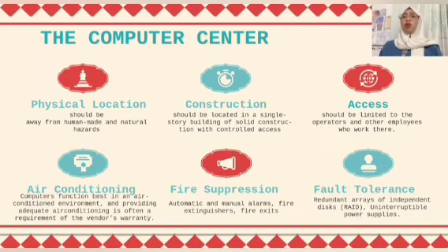The physical location of the computer center directly affects the risk of destruction from a natural or man-made disaster. To the extent possible, the computer center should be away from human-made and natural hazards such as processing plants, gas and water mains, airports, high crime areas, floodplains, and geological faults. The center should be away from normal traffic, such as on the top floor of a building or in a separate self-contained building. Locating a computer in the basement of a building increases its risk to floods.